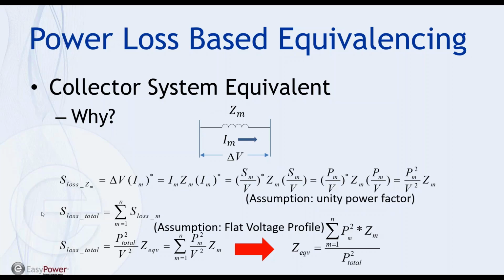Apply the same circuit story to the lumped equivalent circuit. You can see that the total power flowing through the circuit is P total, squared, divided by the voltage squared times the impedance of your collector system equivalent. Now that's the loss on the collector system equivalent. That should be equal to the system total loss, which is the sum of Pm squared divided by V squared times Zm for each circuit. So that's how we come up with this equation. And if we keep assuming that the voltage profile is flat, which means that the V squared on the left-hand side of the equation equals the V squared on the right-hand side, we derive that the collector system equivalent impedance is equal to the sum product of P squared and the impedance Zm of each circuit divided by P total squared. So that's the process of deriving this equation.